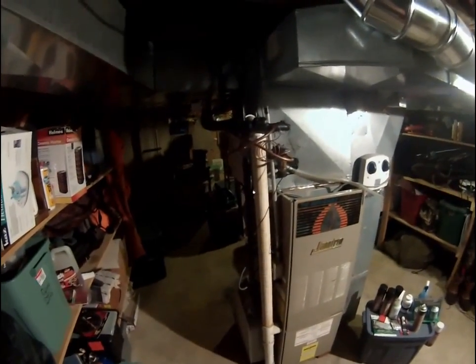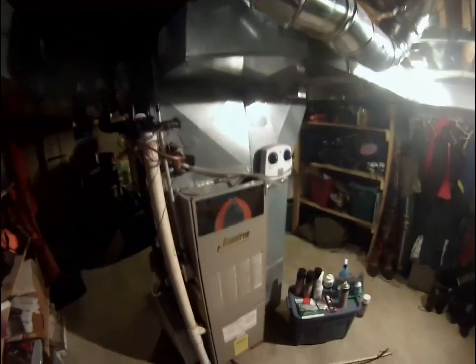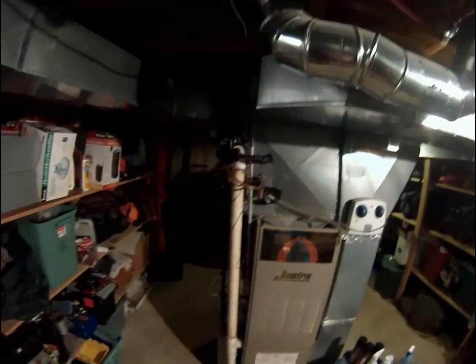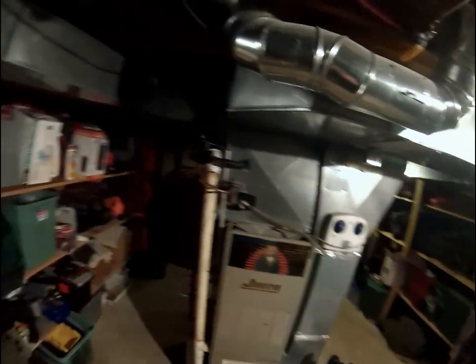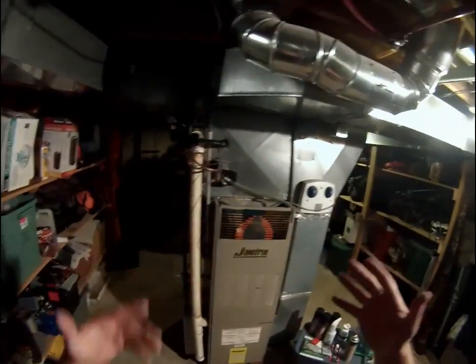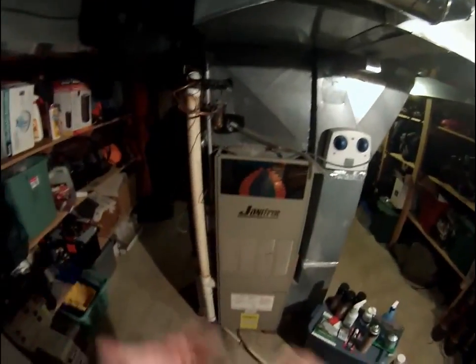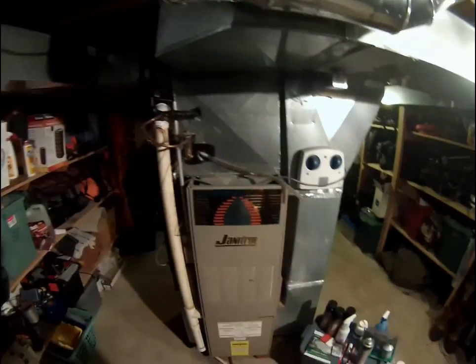That pretty much covers a lot of the air conditioning freeze-up problems that you could run into. We have a zone system on this one where we have dampers, so in the event that those dampers were to fail and close, you would go back to an airflow problem because they would be closed. You wouldn't have any airflow, so that also could cause it to freeze up.